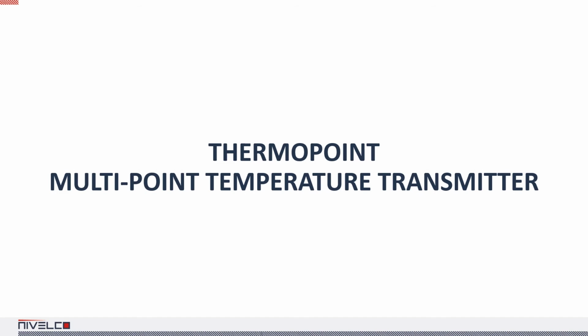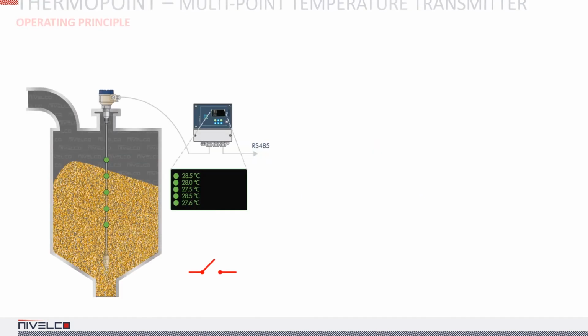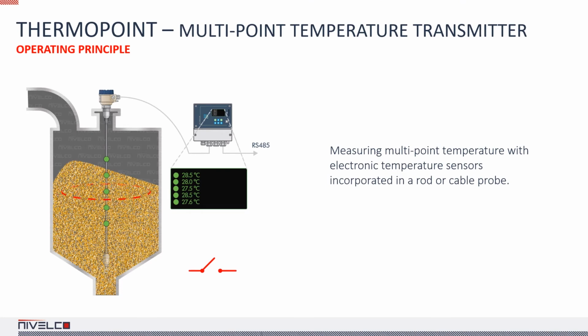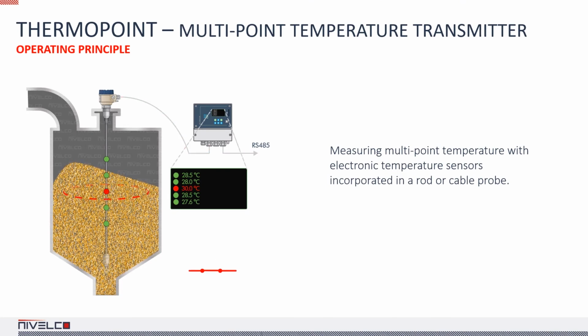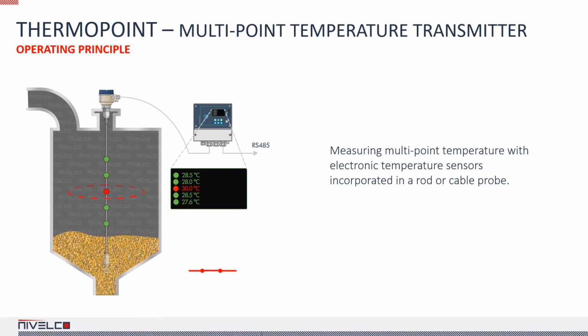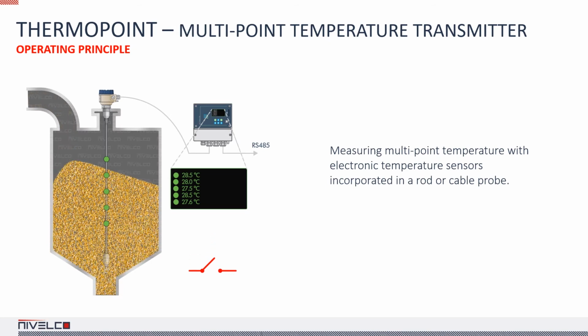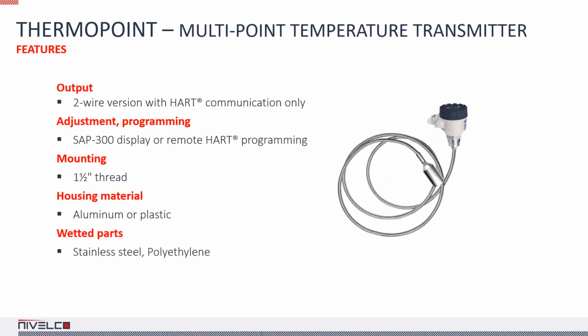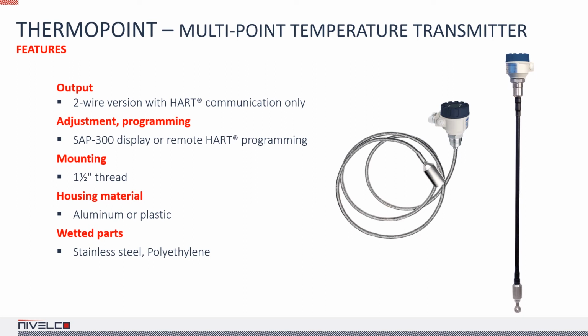Thermopoint 2-wire temperature transmitters are suitable for continuous multi-point temperature measurement of ordinary and hazardous liquids, powders, and granular solids. The temperature of grains and feed stored in silos has to be monitored to maintain their quality. Monitoring the total volume of the silo must provide information on accidental quality loss or the presence of germs or fungus. The 2-wire loop-operated transmitter head can communicate through HART with a MultiCONT process controller or a PC for data processing and logging. A notable advantage of MultiCONT-based systems is that if level measurement is required, the system can be extended with a level transmitter, and that multiple transmitters can be added to the loop using the existing HART communication.